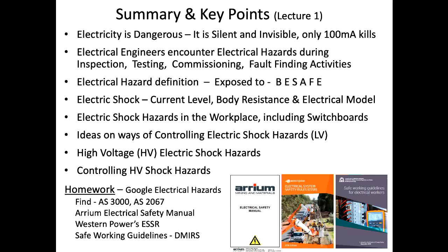So electric shocks, current level, we've talked about that. Say 100 milliamps, you've got to watch anything above 30 milliamps. Now that 30 milliamps is an interesting number, because it comes back when you look at RCDs, and you'll find that it'll try and trip below 30 milliamps. That's the reason why they're designed that way, and I can show you a little bit more about that. So there are reasons for all this sort of stuff.